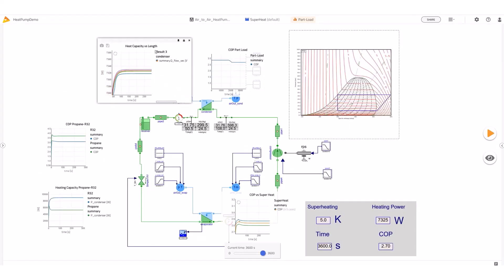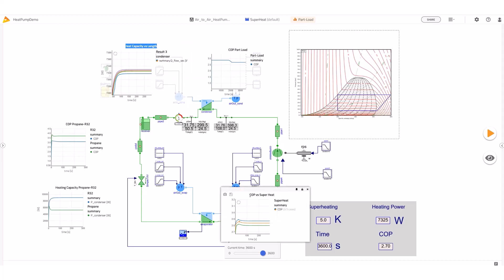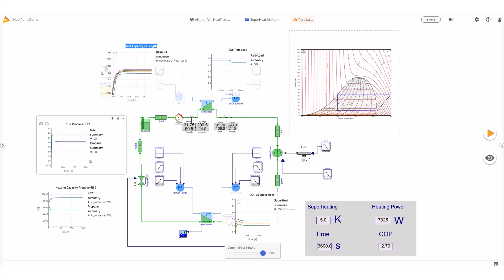Let's summarize the results from the design exploration. We could identify that the condenser was undersized, and thus we doubled the length of the tubes. We also identified that higher superheat levels reduce the system performance, and we decided to maintain around 5 degrees of superheat temperature — necessary to protect the compressor from slugging. Then, when the airflow at the condenser is reduced, the system performance decreases rapidly, which confirms the importance of avoiding potential air blockage.